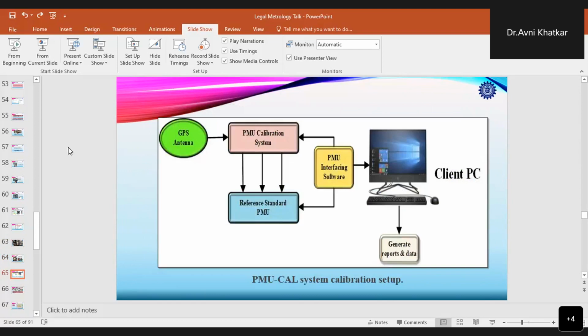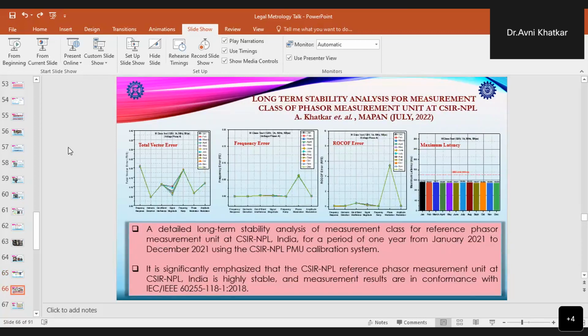This is the setup of the PMU calibration system. In this way, we generate all the reports and data by using the PMU calibration system. All the inputs are time stamped to GPS. These are the results of long-term stability and analysis of the measurement class of PMUs, which was done at NPL. These results were carried out for a period of 1 year, from January 21 to December 21, using the CSIR NPL PMU calibration system. These results significantly emphasize that the CSIR NPL reference PMU is very stable, and all the measurement results are in conformance with the IEEE standard.